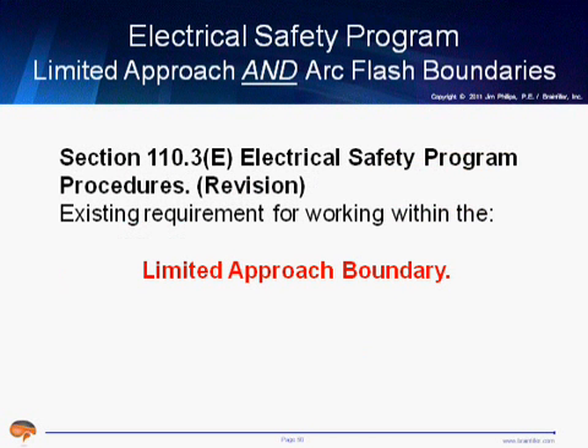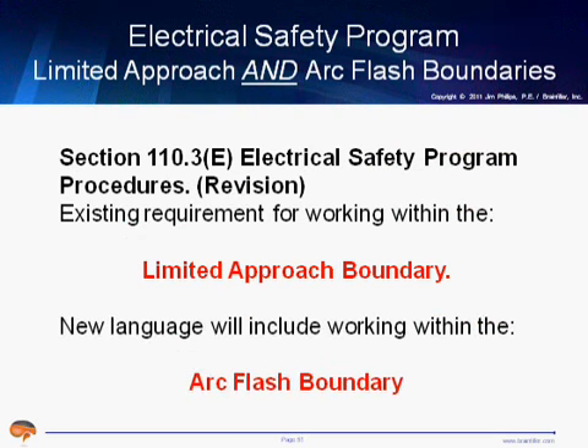And another change, the electrical safety program. The electrical safety program has been applicable anytime someone's within the limited approach boundary, but now in 2012, it's the limited approach boundary and/or the arc flash boundary. Really, it's whichever one is going to be greater. And here's the problem that this is actually going to be solving. I have, we'll say, a representative panel on the right side of the screen. Up until now, this was applicable when people are inside the limited approach boundary, and unqualified people were supposed to stay beyond the limited approach boundary.